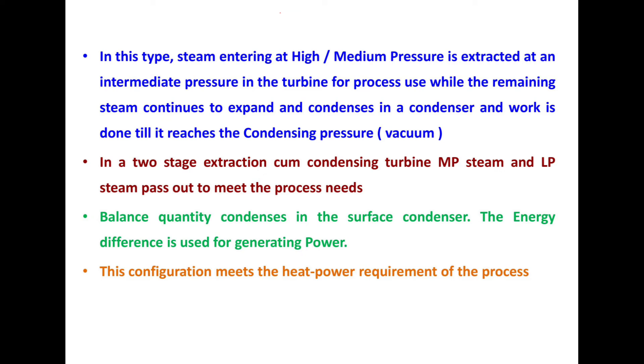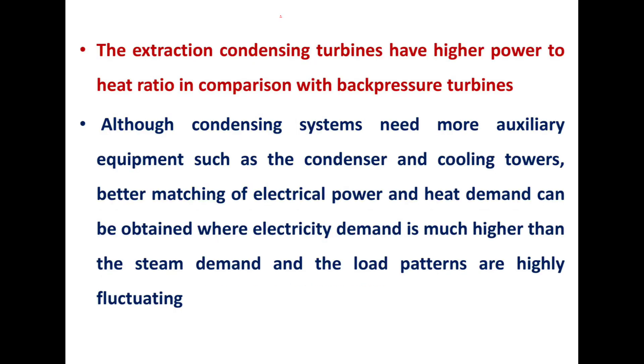In a two-stage extraction condensing turbine, steam enters at high or medium pressure and is extracted at an intermediate pressure for process use, while the remaining steam continues to expand and condenses in a condenser until it reaches the condensing pressure vacuum. Medium pressure (MP) steam and lower pressure (LP) steam pass out to meet process needs, with the balance quantity condensed in a surface condenser. The extraction condensing turbine has a higher power-to-heat ratio compared to backpressure turbines, and although it needs more auxiliary equipment such as a condenser and cooling tower, it better matches electrical power and heat demand where electricity demand is much higher than steam demand and load patterns are highly fluctuating.